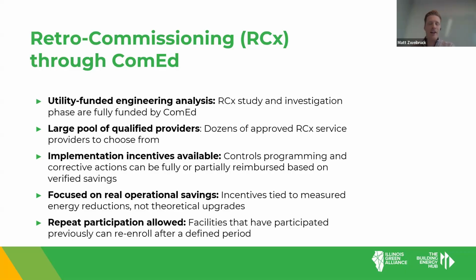If you need to go out and buy a new sensor, or program a new sequence and do some testing around that, they're willing to pay some of that back based on the amount of savings your building is receiving. I like this because it's very direct. It happens, we get to actually see the savings. It's not just handing off an energy audit report that you think does a good job but gets thrown in a drawer, or is only for compliance. RCX is a very data-driven process that takes it from investigation all the way through implementation and verification, so it's really holistic in that regard.